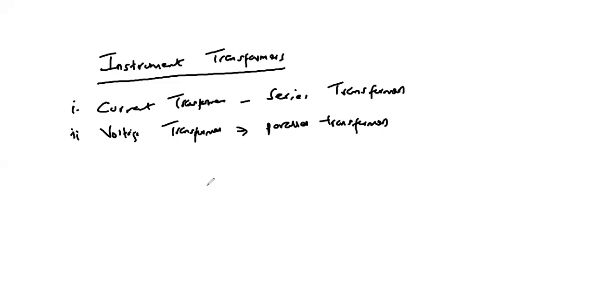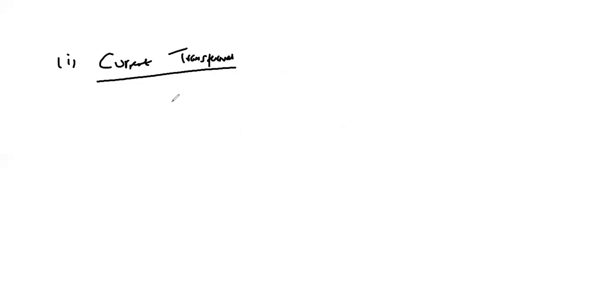Potential or voltage transformers are used where the voltage of the AC circuit exceeds 750 volts, since it is not possible to adequately insulate the measuring system for voltages higher than 750 volts. We will look at the configuration and operation of each of them, starting with the current transformers in measurement of heavy currents.